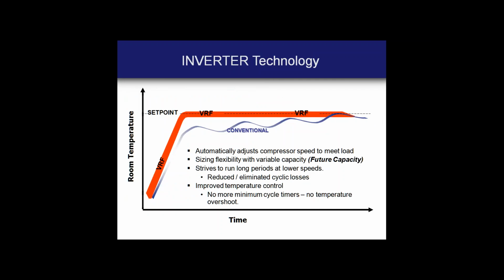Again, at the heart of this technology is that inverter-driven scroll compressor. So the ability to ramp up quickly and then modulate and maintain set point over long periods of time, elimination of those cyclical losses associated with conventional staged DX equipment.